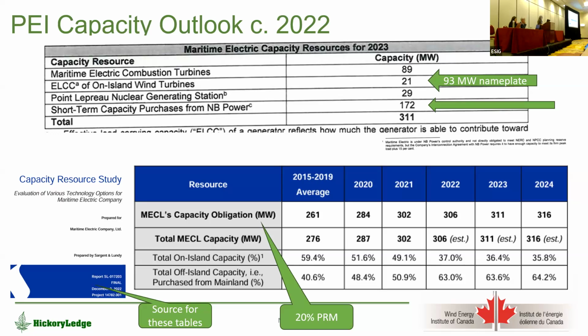In 2022, Sargent and Lundy were commissioned to run a capacity resource study, and the capacity obligation for 2023 was set at 311 megawatts, reflecting a planning reserve margin of 20%. This top table shows what makes up that 311 megawatts: 89 megawatts of on-island combustion turbines that rarely run and are expensive, and 93 megawatts of nameplate wind on the island—but when you calculate the capacity value of that wind, it's only 21 megawatts of effective load carrying capability.